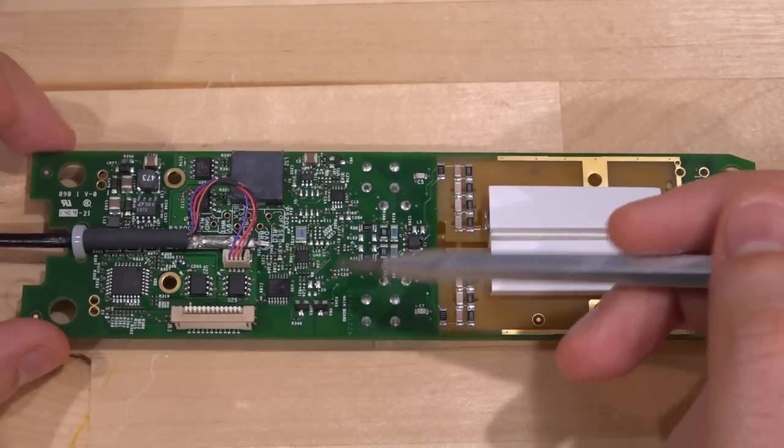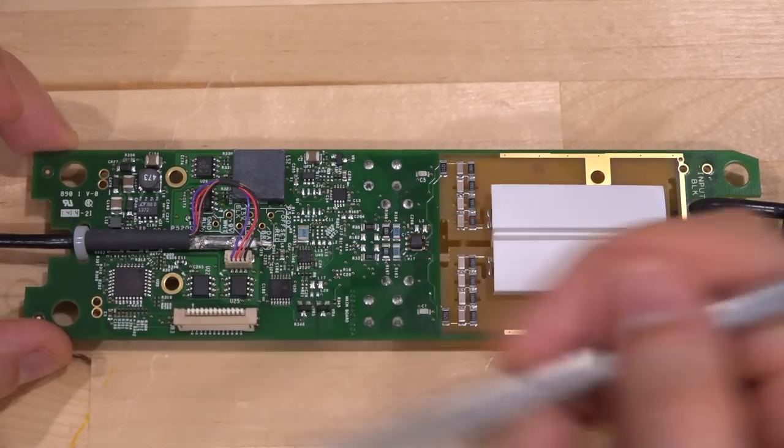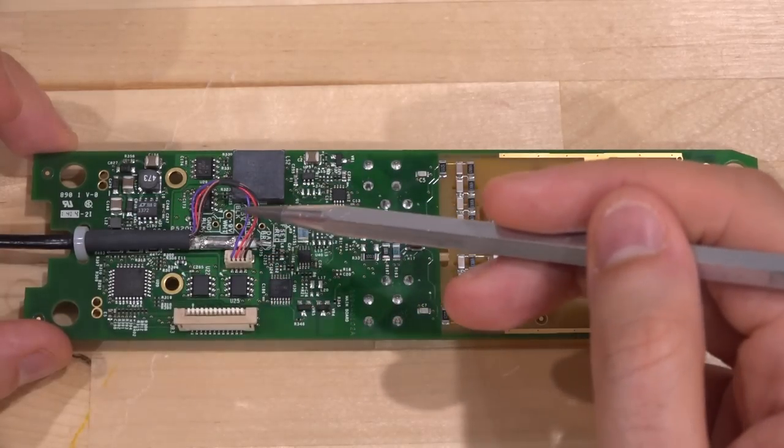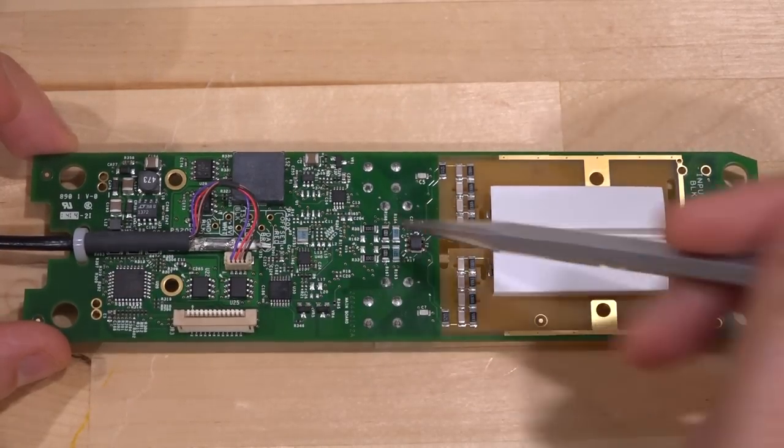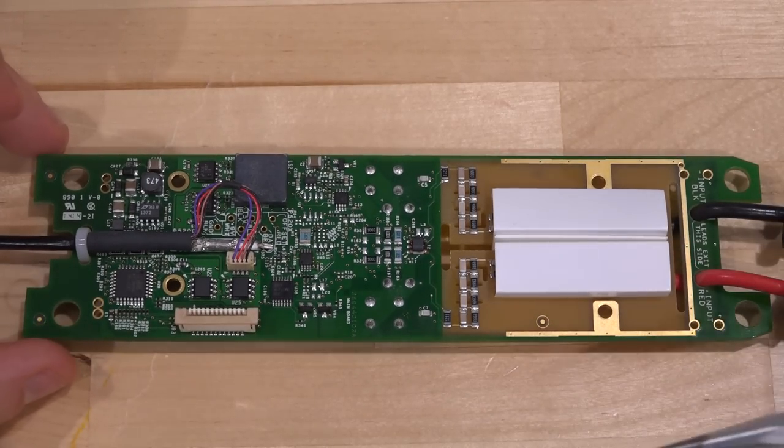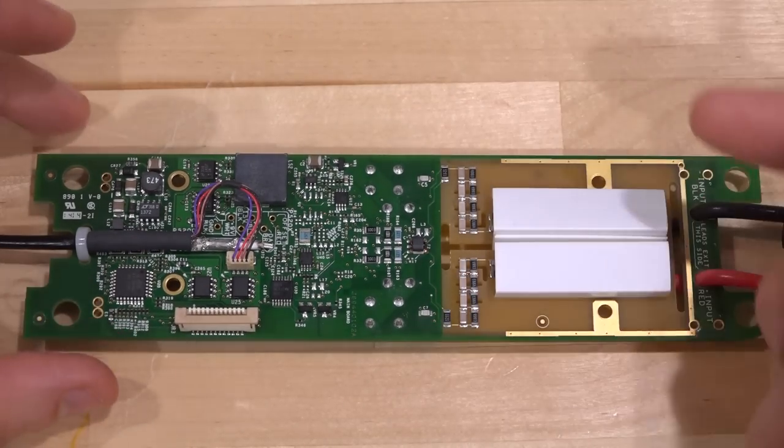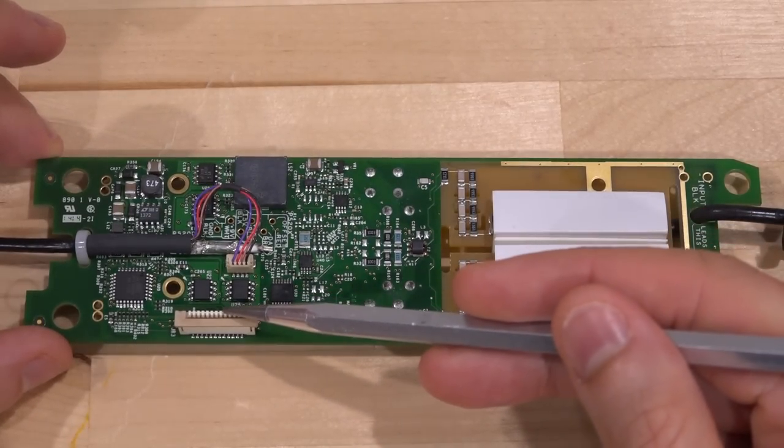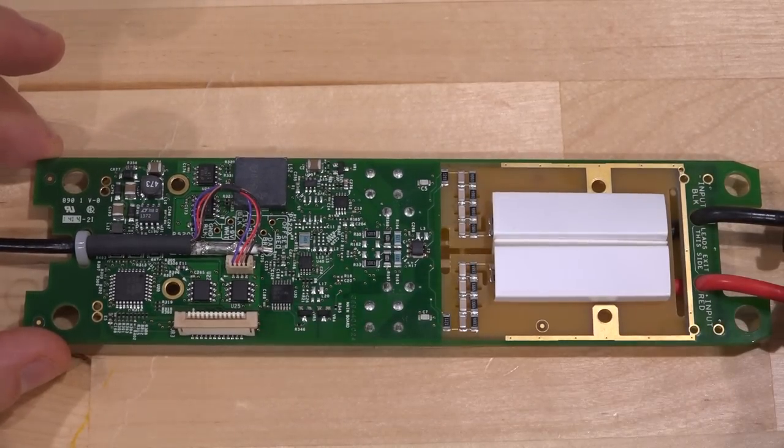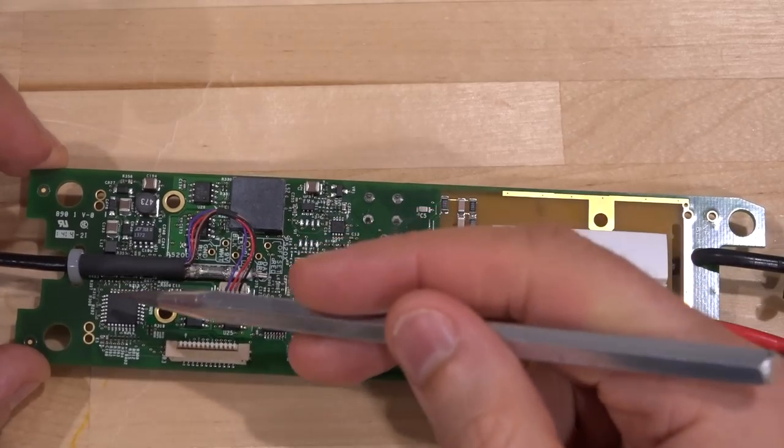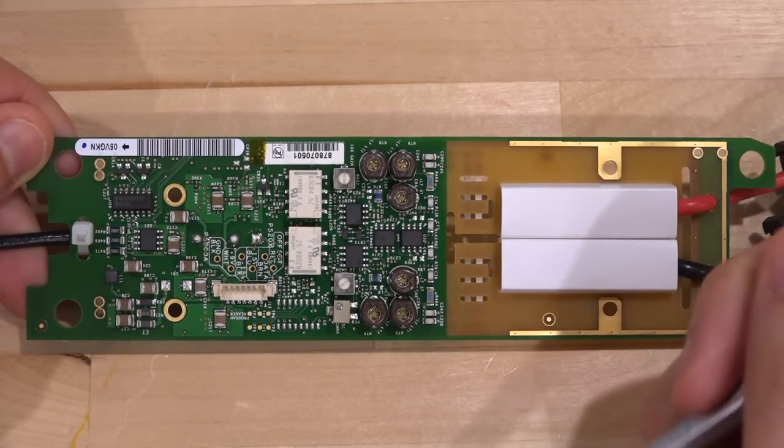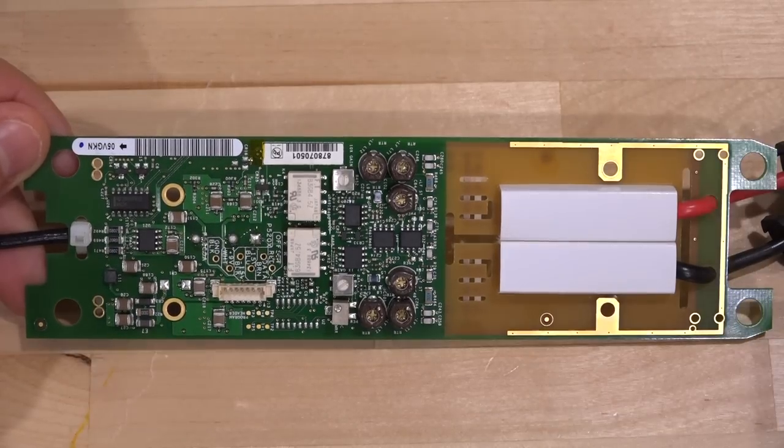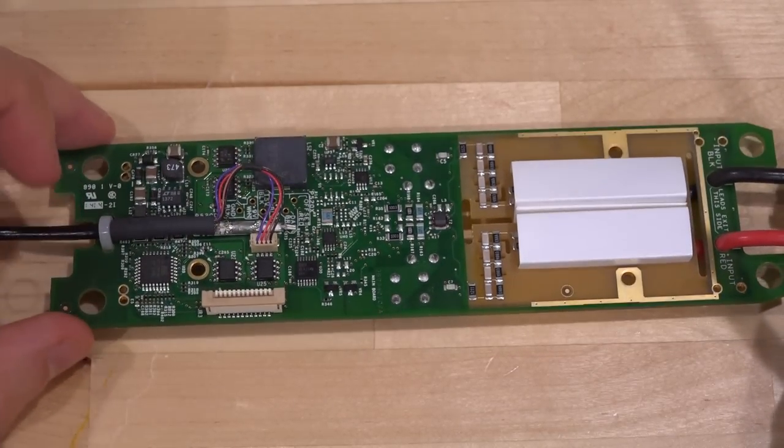We have potentiometers that you can tune to get rid of various offsets and common mode adjustments and gain adjustments, some relays for range switching, and that's about it. Then signal eventually ends up in the coaxial cable over here. There's some power supply conditioning as well because you need to bring the power supply voltages up or down depending on what's running. Here is another microprocessor. The serial data coming over here communicates with this guy, and this guy then controls all the relays and everything else in order to make sure that you set the range. This also has a programming port here which is exactly the same pinout.